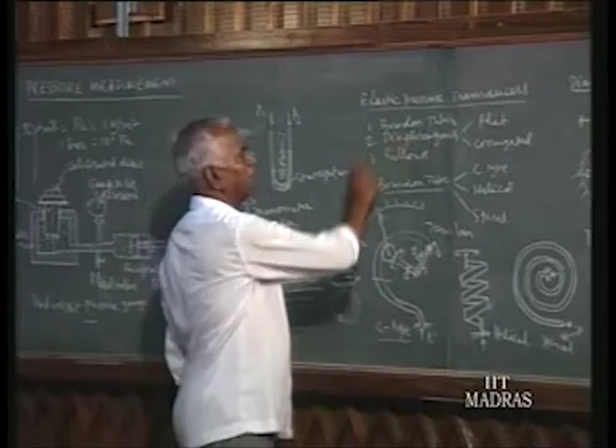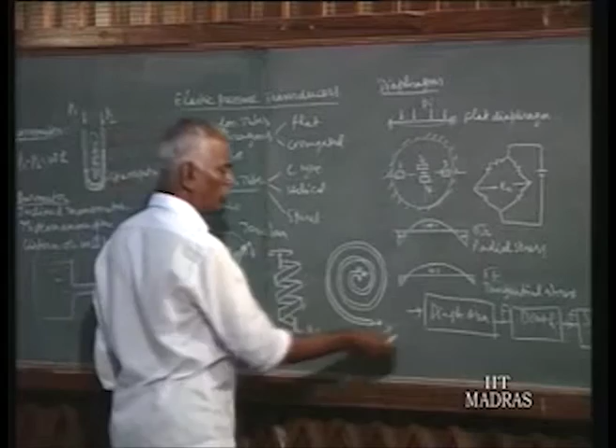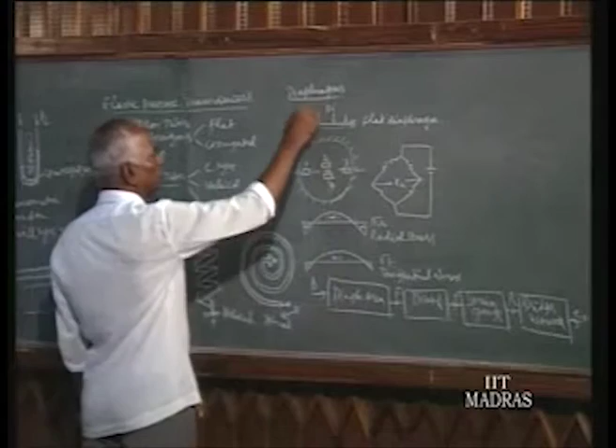So the next one is the diaphragm. We have got two types of diaphragm, flat diaphragm and corrugated diaphragm. A flat diaphragm is just a thin sheet, again made of spring material, fixed at the rim. When you apply pressure on one side, you find it deforming like this, and that means the pressure is converted into force according to this signal flow diagram. When we apply pressure over an area, it converts into force: pressure times the area of the diaphragm. That force deforms the diaphragm material.